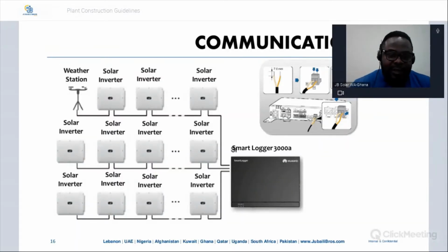Let's focus more on the Smart Logger 3000A. As I mentioned, it can take up to 80 inverters in a synchro. It has 3 communication ports under the logger: COM port 1, COM port 2, COM port 3. Each communication port can manage up to 30 inverters in a daisy chain, but the total overall is 80.